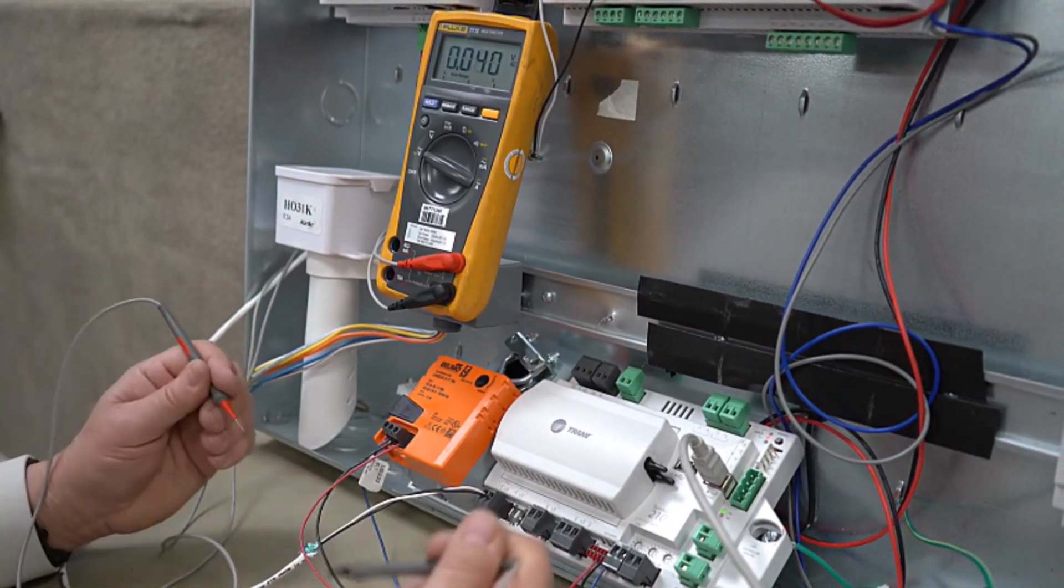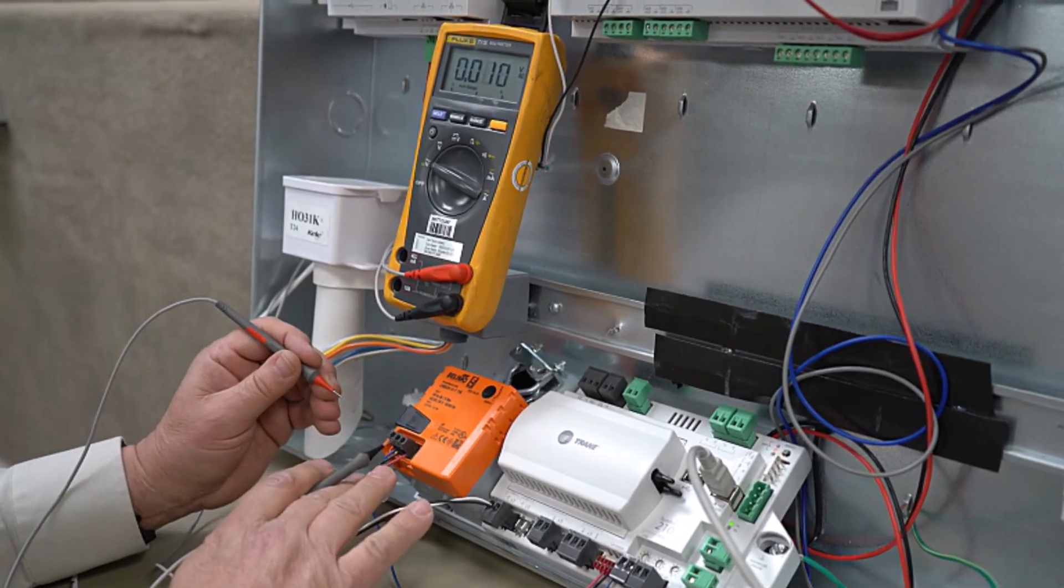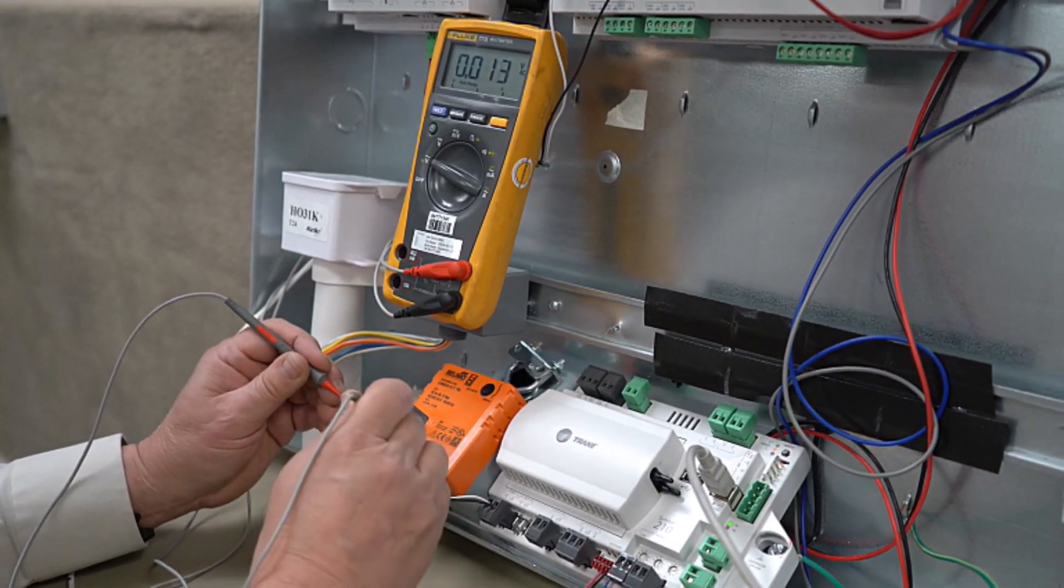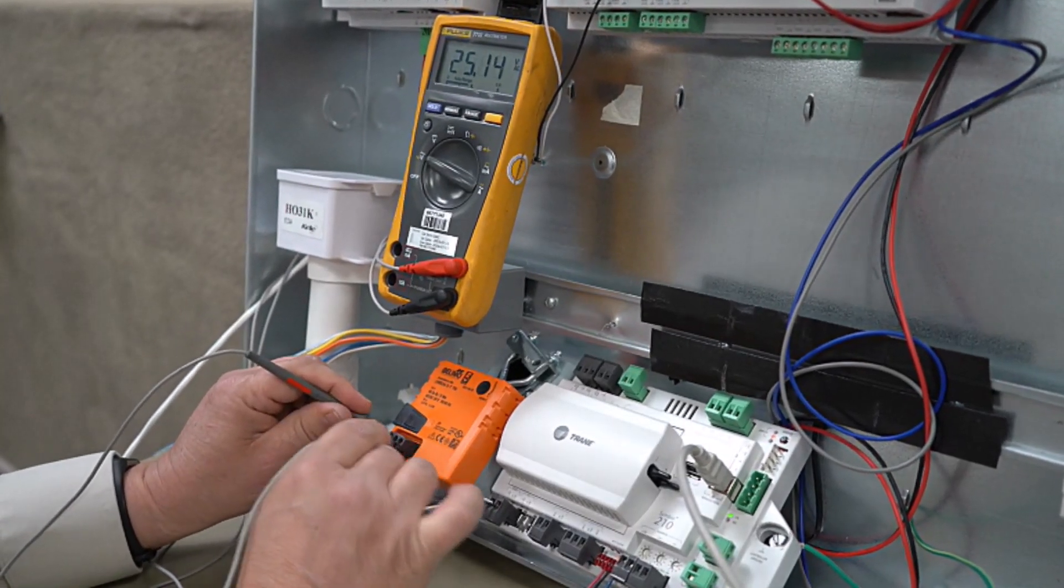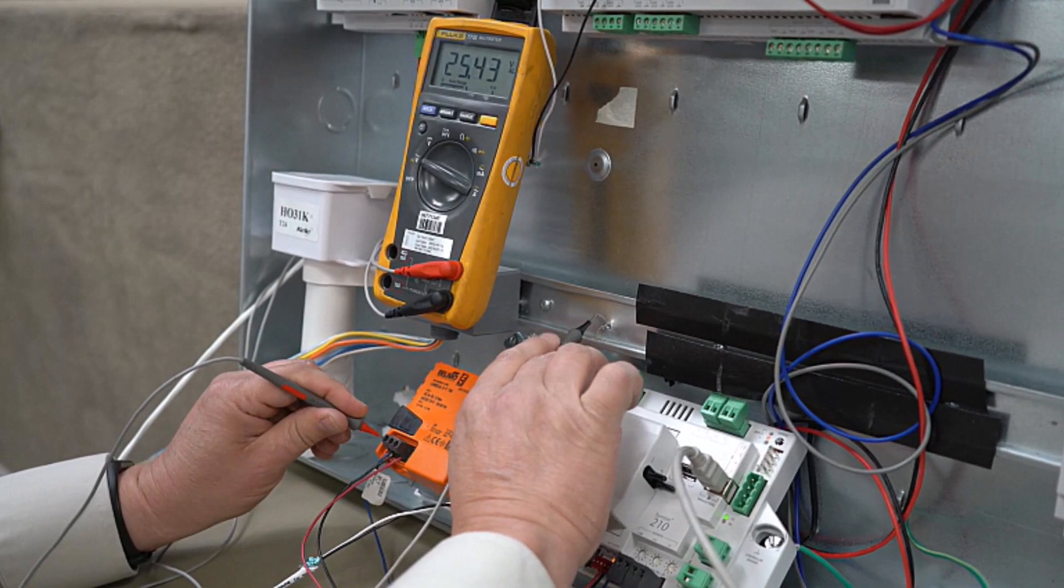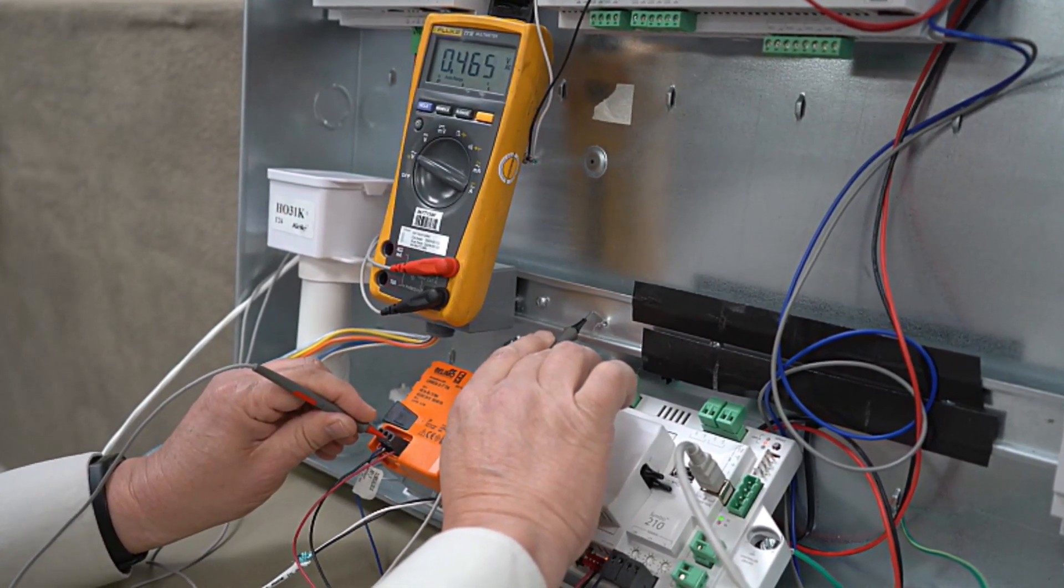When we reverse directions and we drive it the other direction, then that common is going to change from the black wire to this red wire. So off of here, we still have that 25 volts from the blue to the red. Blue is still our hot leg at 25 volts and that red wire has now become our common as the actuator drives in the other direction.